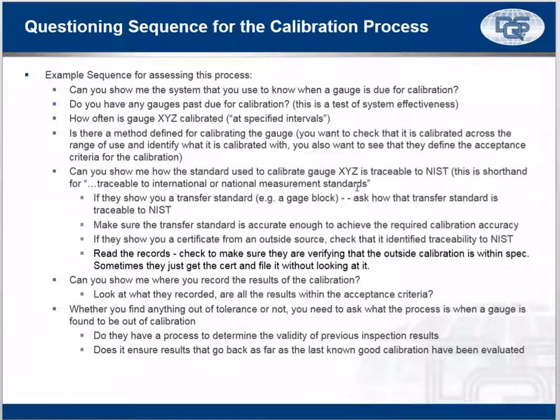Generally, your transfer standards are going to have external calibration, so they send them out of house to be calibrated. You will want to take a look at the certificate. When you get that certificate, you need to make sure that you check it and see that it has traceability to NIST. I'm just going to shorthand it again. You need to read the record and make sure that that external record that you're looking at doesn't have things that are outside spec. So don't just get a look at it. It should have actual as found results. That's what you're looking at to make sure that they were good as found. There wasn't an out of tolerance condition.